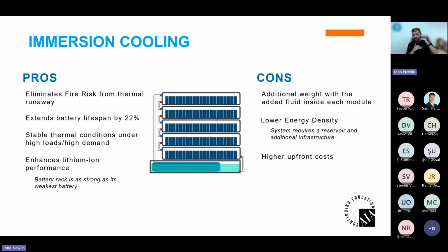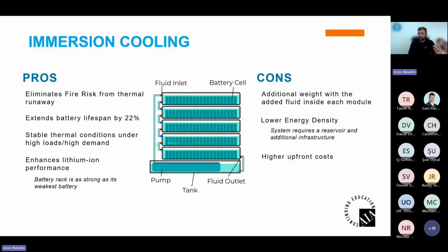Also, the cells are submerged in liquid, so that removes any ignition source from the cells, for example NMC cells, which carry their own ignition, or LFP that might have a short on a bus bar that could cause a spark that could ignite the toxic and flammable gases. So we see that as a massive pro for immersion cooling.